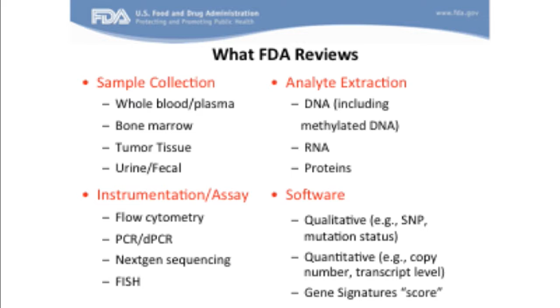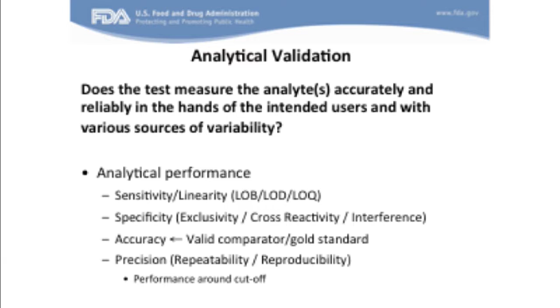So for analytical validation, the question is, does the test measure the analyte accurately and reliably in the hands of the intended users with various sources of variability? Generally, for analytical performance, we look at the sensitivity, linearity, the limit of blank, detection, quantitation, the specificity of your assay in terms of cross-reactivity, interference, exclusivity, the accuracy as compared to a valid comparator or gold standard reference method, and the precision. Can you get the same result reliably if you repeat it? And in a multi-site reproducibility, could you get the same response? And we generally look at performance around the pre-specified clinical decision-making threshold. And this is why the clinical decision-making threshold should be pre-specified ahead of this analytical validation activity and is a key element to designing your medical device.